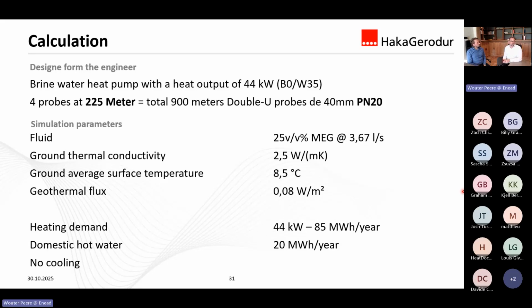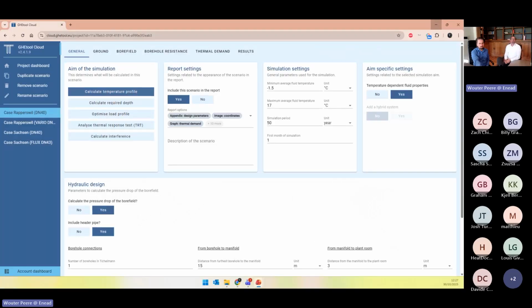The demand for heating is 44 kilowatts, so it's 85 megawatt hours per year. And the domestic hot water is 20 megawatt hours per year, so there is no cooling. And here we see on the upper part for the simulation parameters, we use a brine. So now we go to the GHEtool, and Wouter will show you how to use the GHEtool.